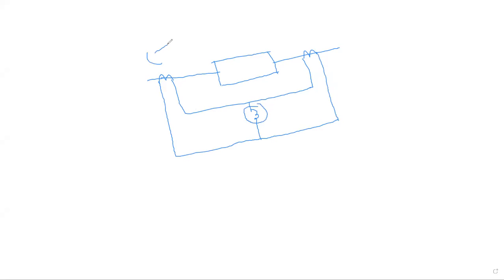First one is that the two CTs, or two instrumentation transformers, should be identical. If not, then though the fault is external, the differential relay would operate. And the second point was that if, in some cases, we consider that these two CTs are properly identical, then due to the connections of the relay, apart from the midpoint, it could raise a different loading of the instrumentation transformer, which can also lead to maloperation of this differential relay during external fault.